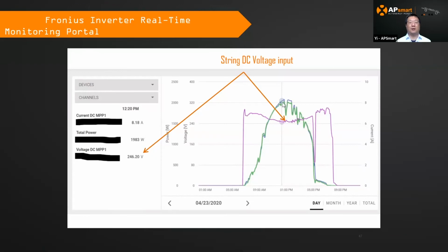Yep, this introduces the Fronius real-time monitoring portal, which you should pay attention to. This is for the DC voltage for each MPPT level. That's the number you need to monitor for the operation of the RSD, because if one RSD fails in the field, it will show up on the voltage input level pretty much. So pay attention to this.